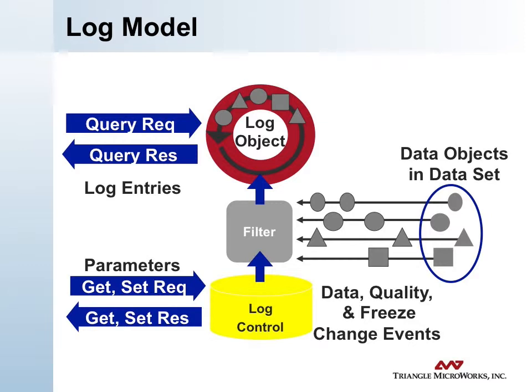These parameters on some limited devices may not be writable. They may be configurable through the substation configuration language file, in which case it's managed at config time, not at run time. So the get and set requests on the control block would not be done real time in the network — it would be configured ahead of time.